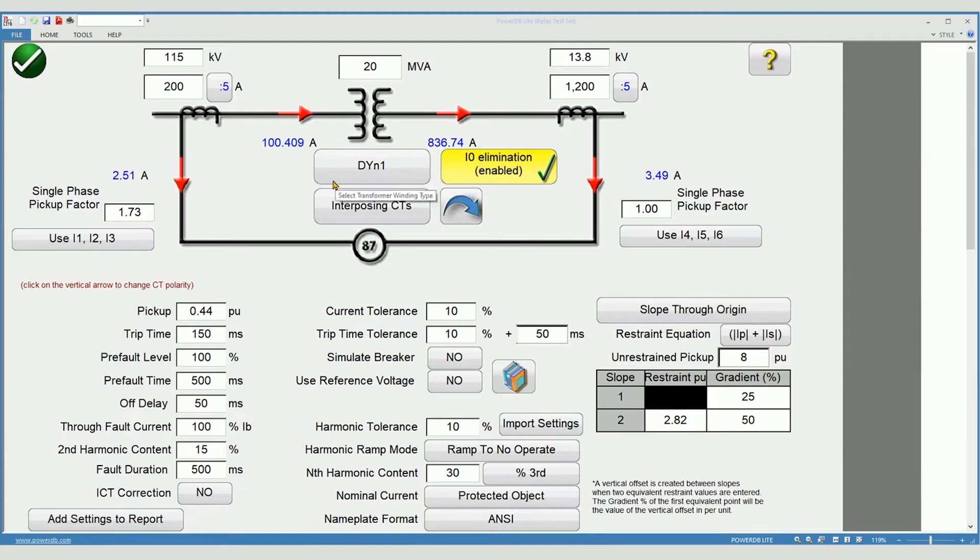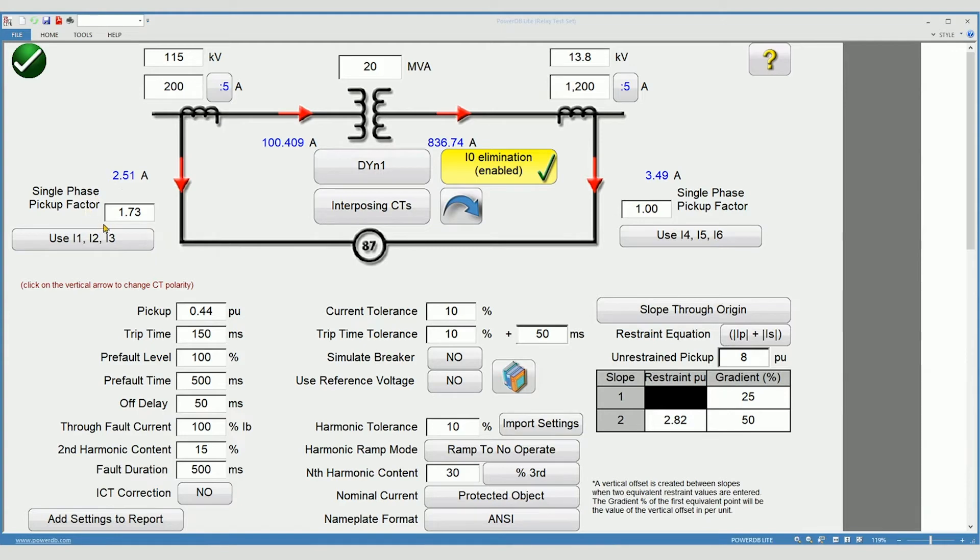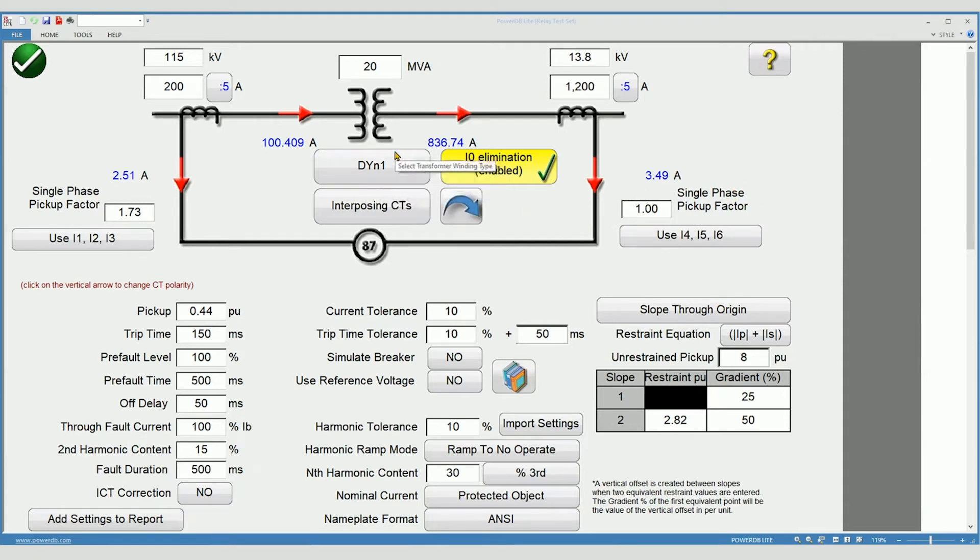Modern relays actually use symmetrical components for calculating differentials. When applying single-phase current, the currents must be compensated for this. The compensation factors shown are the most common compensation factors based on the transformer type and the CT connections.